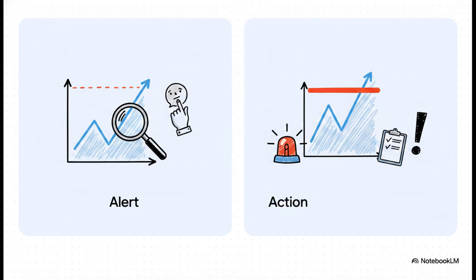An alert limit gives you an early warning of drift. Your process is still technically in control, but it's moving in the wrong direction, and that prompts a proactive review. An action limit, however, means you have crossed the line. Control has been breached, and this demands an immediate, formal investigation and a defined corrective action. Defining these limits correctly based on your own facility's capability and your CCS is paramount.